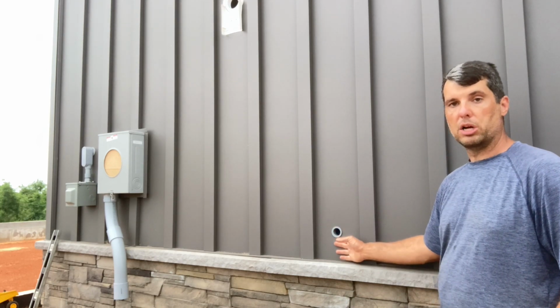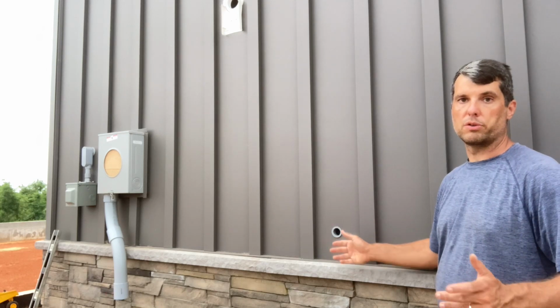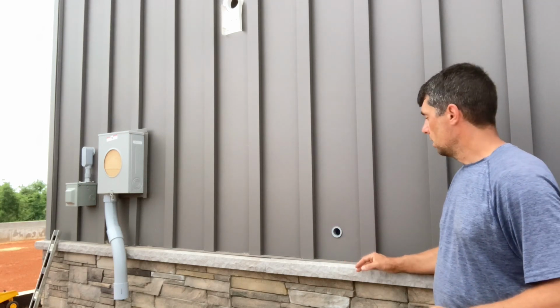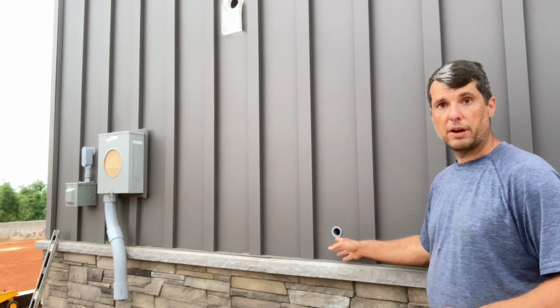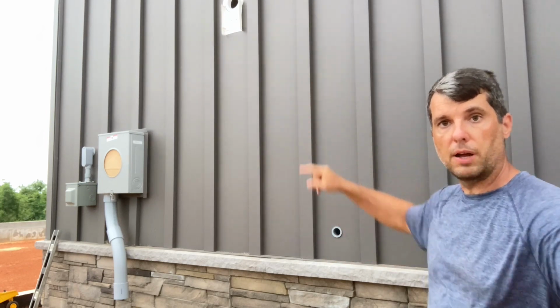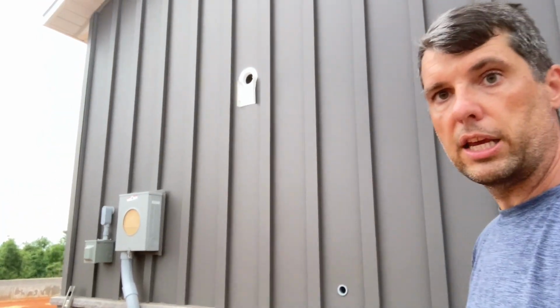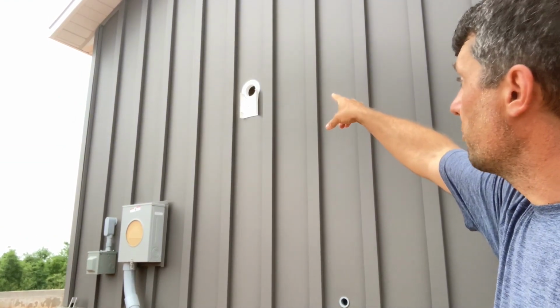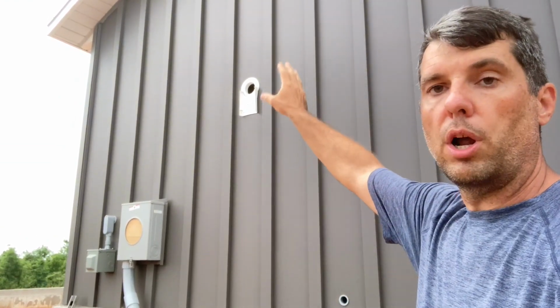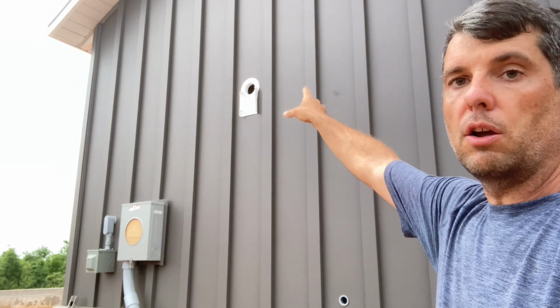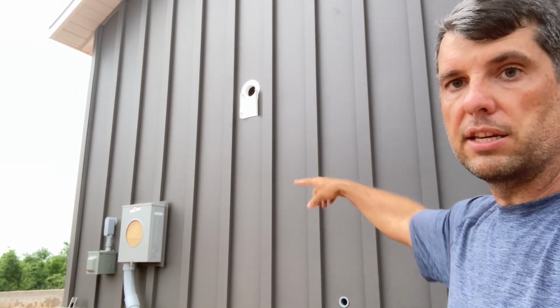They just want to see the hole punched, where it's going to be, make sure structurally I didn't do anything to the building. So I have this in, and you can see up above, it's off screen just slightly. That's a 3.5 inch hole, and that's where my line set will run from the head on the inside to the condenser on the outside.